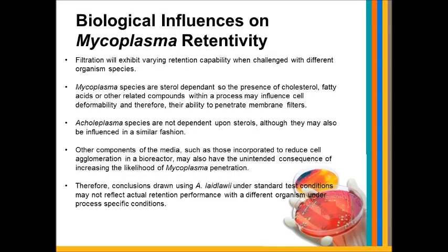So, biological influences on mycoplasma retentivity. Filtration will exhibit varying retention capability when challenged with different organism species. As I mentioned, with what the PDA subcommittee is looking at with laidlawii, under those test conditions, I believe we ran at about 30 pounds differential, and we're still able to retain 10 to the 10th of that particular organism.